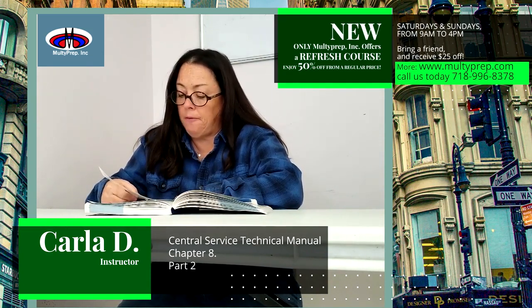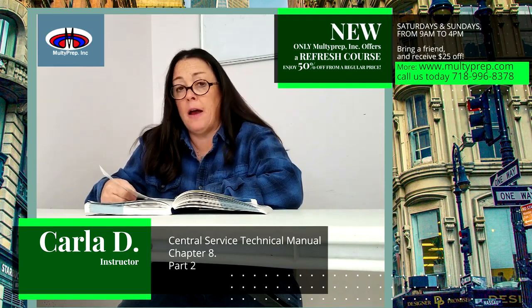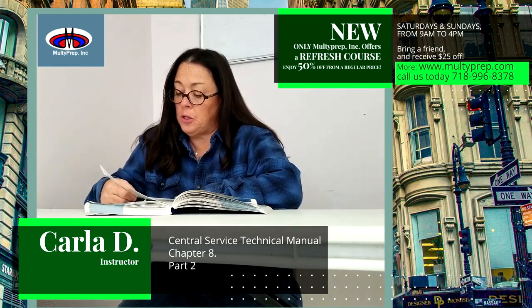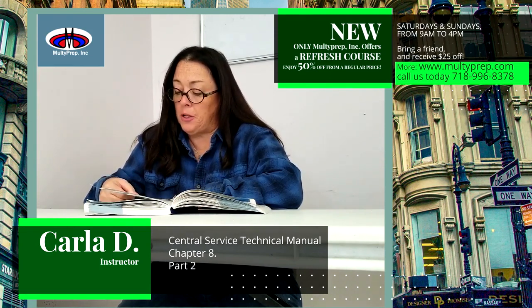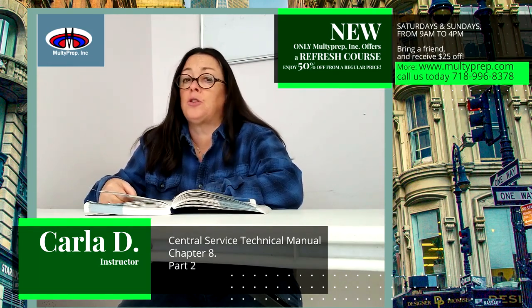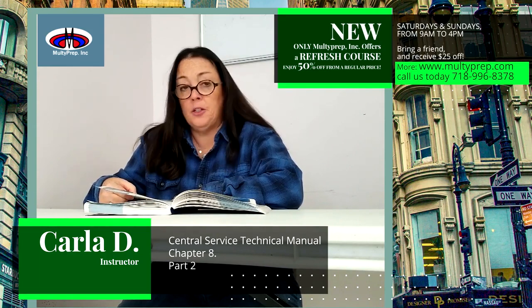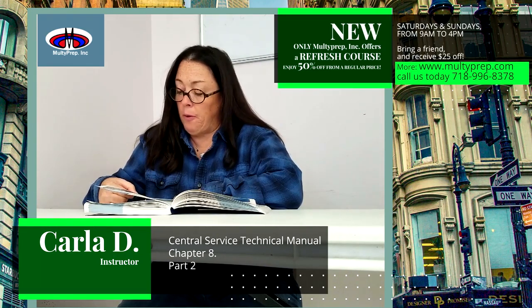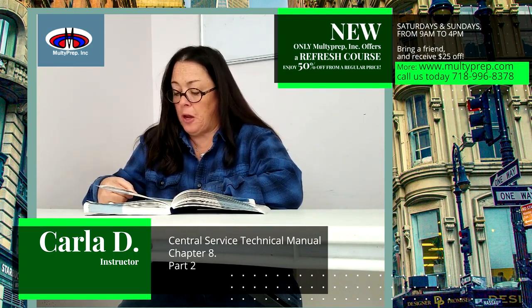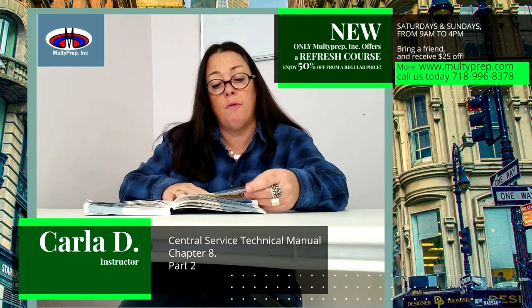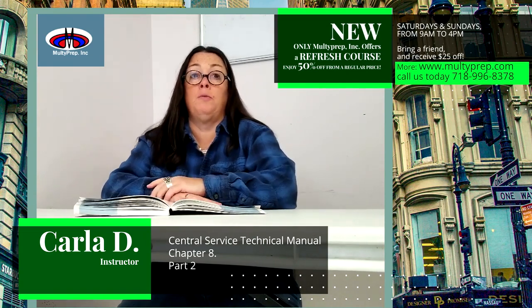Alkaline detergents are highly effective at removing organic soils such as blood, fat, and oils. Alkaline detergents range in pH from 8 to more than 11. Prior to using an alkaline detergent, refer to the manufacturer's instructions for use. Advantages. Alkaline detergents remove a wider range of soil than any other type of detergent, and they are economical to use and low foaming. Disadvantages. Alkaline detergents require thorough rinsing as they can leave a powdery residue on the instrument surface. Alkaline detergents cannot be used on devices made of bronze, copper, or aluminum.